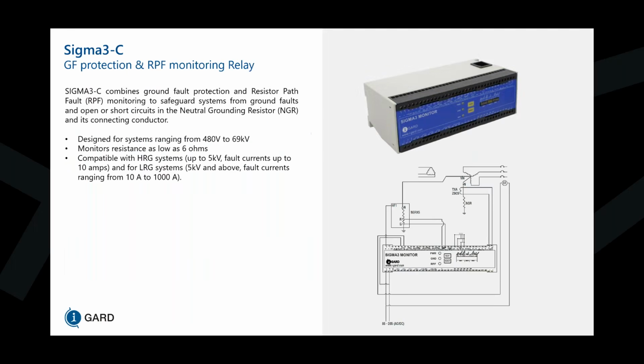Now, for resistor monitoring, we have the Sigma 3C, and it combines ground fault protection and resistor path fault monitoring to safeguard systems from ground faults and open or short circuits in the neutral grounding resistor and its connecting conductor. So in the past, we used to use the term NGR fault, but now we're looking at the entire path from the XO point to ground. And if you look at the Canadian Electrical Code in figure 10-B12 or B10-12, I forgot which one, it says that we have to monitor right from the XO point to the ground. So that means that we have to make two connections to our XO point. One is for our sensing resistor, and one is for our NGR.